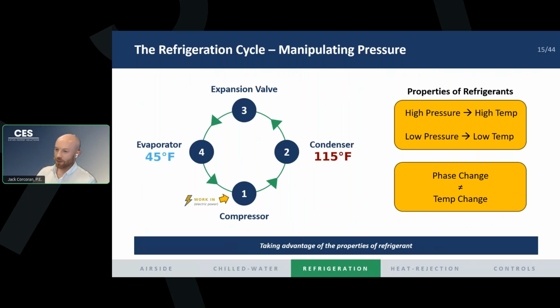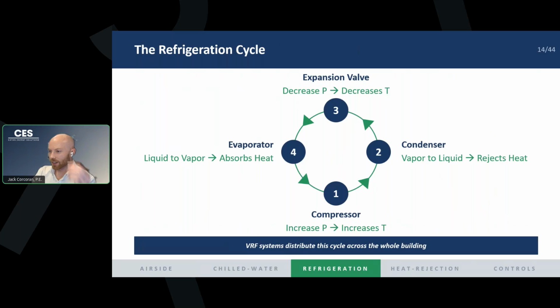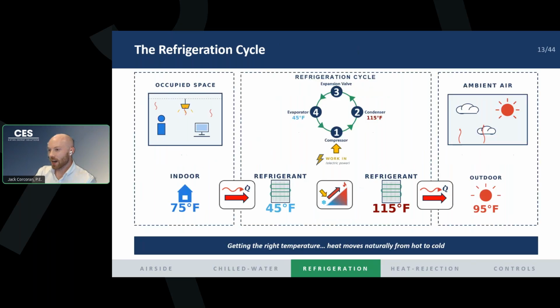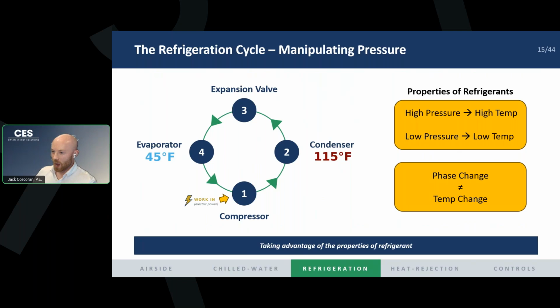And it's the same thing on the reverse side of the loop, in stage number 3, the expansion valve. All we're doing is reducing the pressure in order to lower the temperature, to get from that 115 degrees down to 45. We're just taking advantage of the properties of refrigerant in order to make this hot and cold side work for us in a continuous loop. One other important thing to note about the cycle is that we are not changing the temperature when we're changing phase. If we go back to the previous slide, we can see that in our evaporator and our condenser we're changing phase, and in our expansion valve and compressor we're changing pressure. So we're changing the pressure at the top and the bottom, and we're changing the state and phase of the refrigerant on the left and the right.